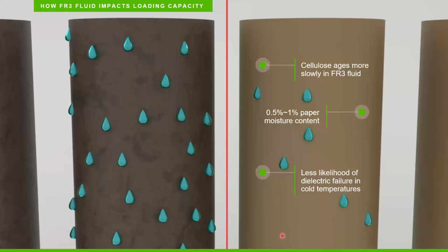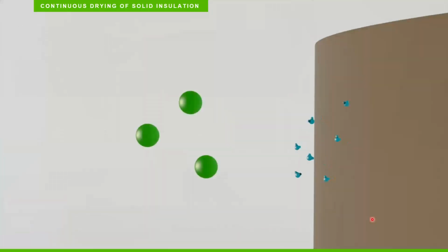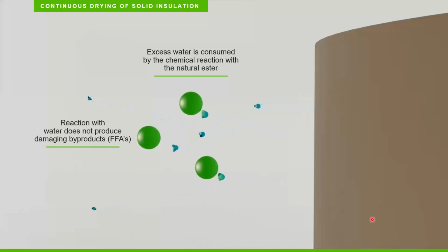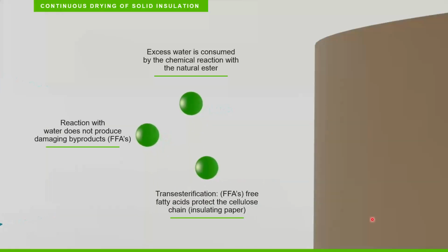And this is not happening with FR3, because with FR3 the moisture content in the paper stays between 0.5 and 1% during the complete lifetime of a transformer. We will see how this works on FR3. But it's also important to note that the reason to dry a transformer is not only to extend paper life. The most important one is the dielectric reason, because wet paper has a worse dielectric behavior compared with dry paper. So with FR3, we can maintain a good dielectric condition during the complete lifetime of a transformer, increasing reliability, as we spoke about at the beginning.